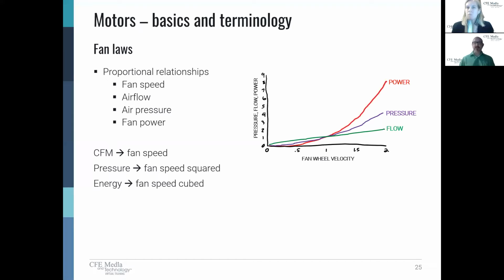Now, the important takeaways here are this very expertly drawn graph where we can see that CFM or flow is proportional to fan speed. Pressure is related to the square of fan speed. And energy, power, or horsepower, for example, is related to the cube of fan speed. That's kind of the basics of what that looks like. Obviously, as you're doing all of your calculations, you're going to be utilizing that information to determine, if I change this, what's going to happen.